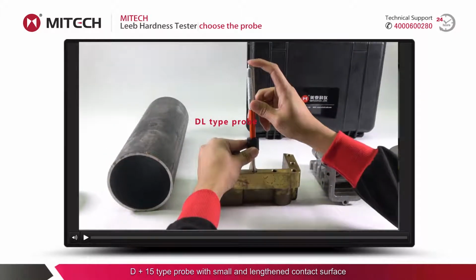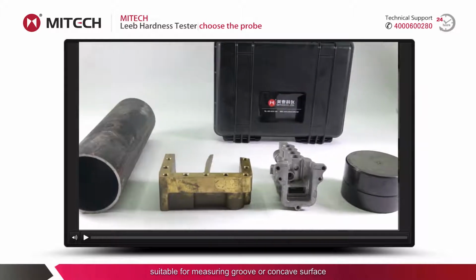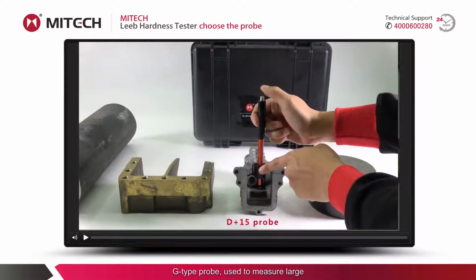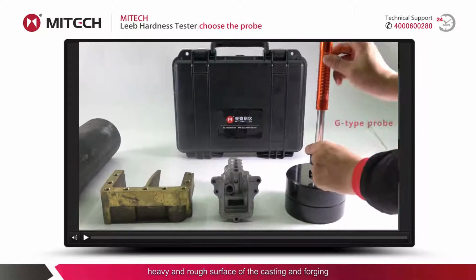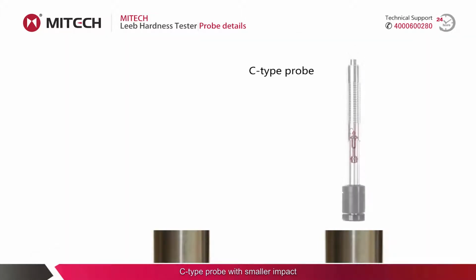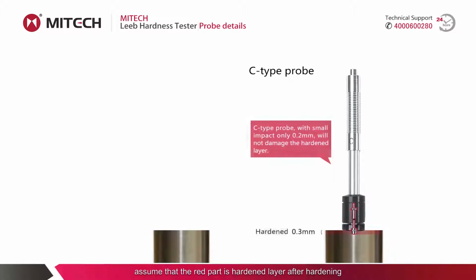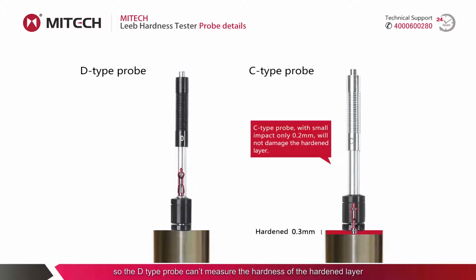The D+15 type probe, with a small and lengthened contact surface, is suitable for measuring grooves or concave surfaces. The G-type probe is used to measure the large, heavy, and rough surfaces of castings and forgings. The C-type probe has a smaller impact, so it causes less damage to the measured surface and does not damage the hardened layer. It is suitable for measuring small, thin workpieces and surface hardened layers, as shown in the figure. Assume that the red part is the hardened layer after hardening, all within 0.3 mm. With the conventional D-type probe, the depth of the ball hitting the workpiece surface is 0.8 mm, so the D-type probe can't measure the hardness of the hardened layer.